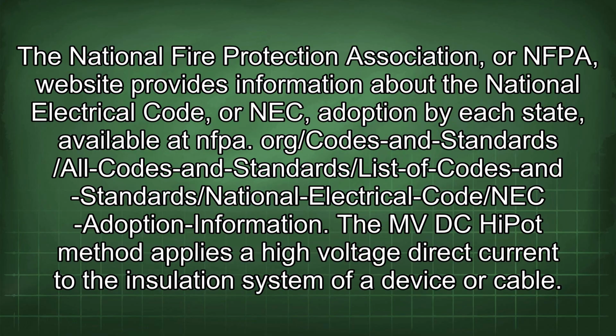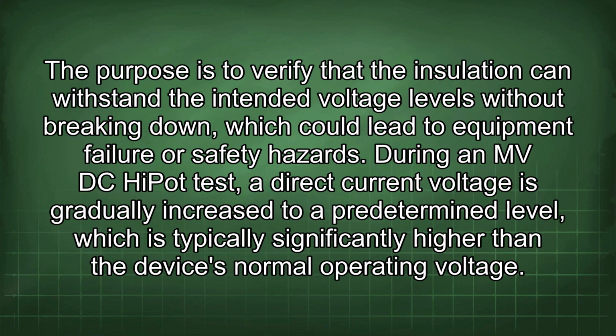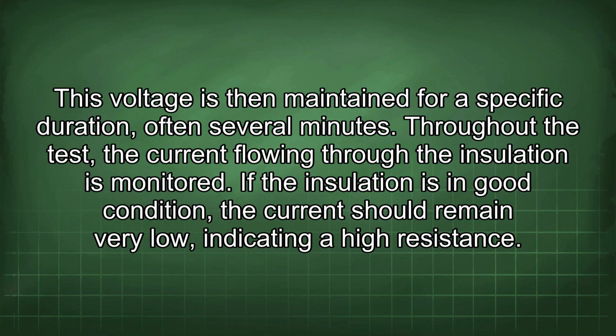The MVDC HiPot method applies a high voltage direct current to the insulation system of a device or cable. The purpose is to verify that the insulation can withstand the intended voltage levels without breaking down, which could lead to equipment failure or safety hazards. During an MVDC HiPot test, a direct current voltage is gradually increased to a predetermined level, which is typically significantly higher than the device's normal operating voltage. This voltage is then maintained for a specific duration, often several minutes.